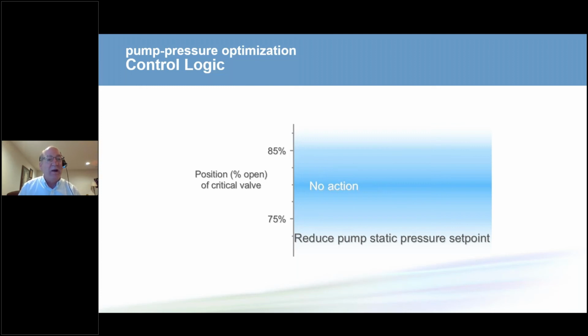Why do we want to do that? Well, we didn't have the capability to do this in the past. But now that we know that critical valve position, we reduce the pump static pressure set point, the pump slows down, its power goes down, the pressure goes down, and that valve comes back into the dead band that we want. We're using less pump power. Now, what happens if that critical valve goes above 85% open? Well, we're in danger of losing the load, losing the leaving air temperature, not providing the cooling necessary for the process. So if that critical valve goes above 85% open, we increase the pump static pressure set point until we satisfy that valve and get it back within the dead band.